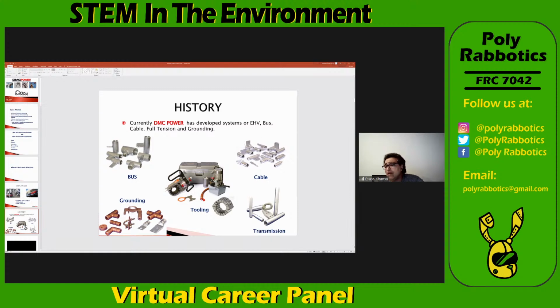Inside a substation you have cables to connect to conduct electricity, and solid members to conduct electricity instead of cable, like solid tubes or flat bars. You can also make connectors to ground the facility. If you have fault current, to keep people from being hurt and equipment from being damaged, you ground it using grounding connectors.